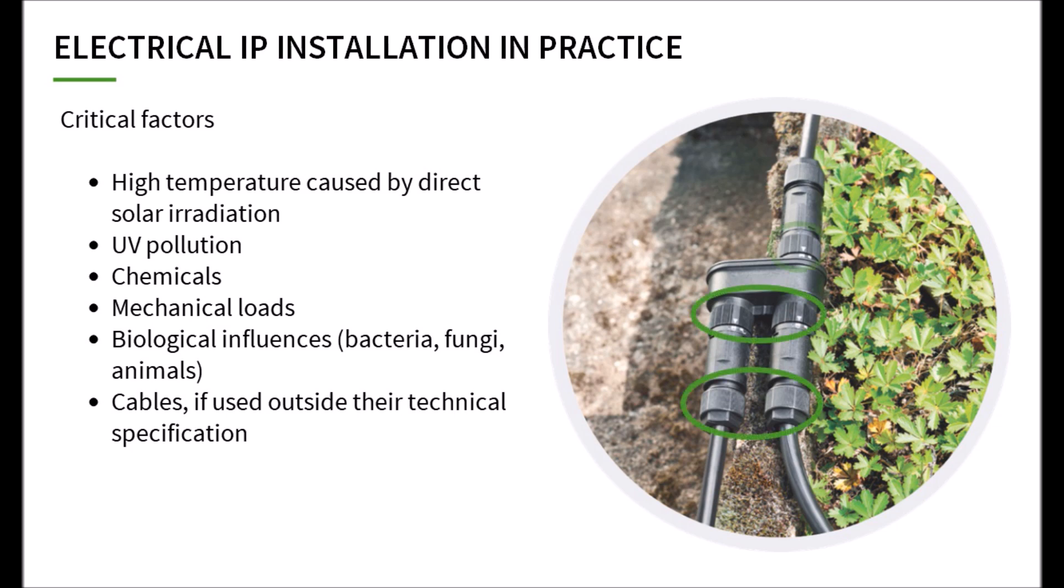Sensitive areas are seals in the area of the plug face and the cable gland. High temperatures due to direct sunlight, high UV concentrations, and other weathering influences but also chemicals affect the seals. Not to forget mechanical stress and biological influences from bacteria, fungi, or animals. The cable is also affected, especially if it is used outside its specifications.